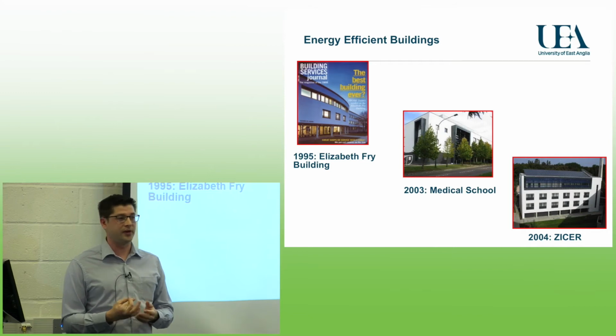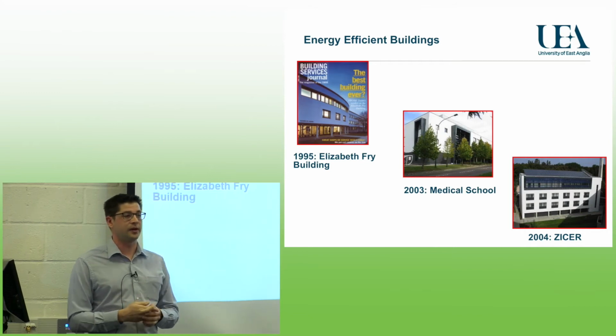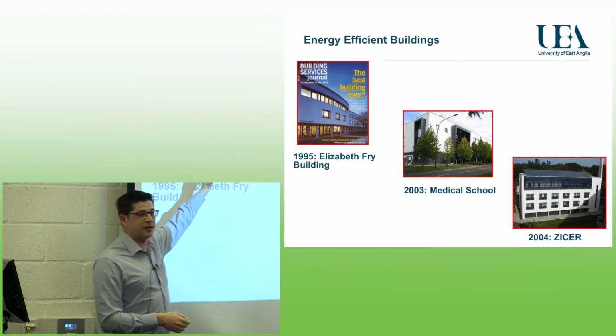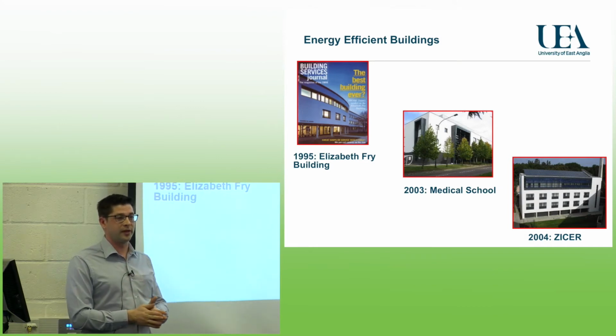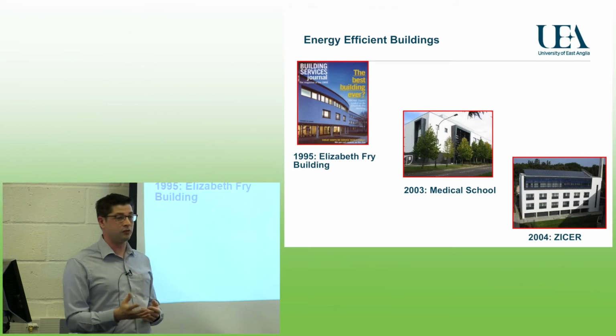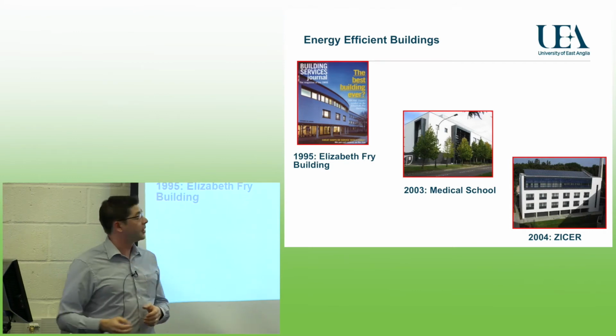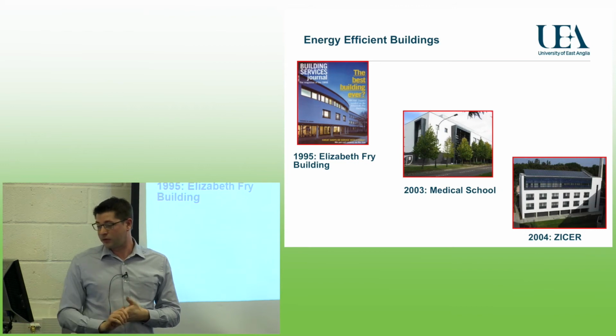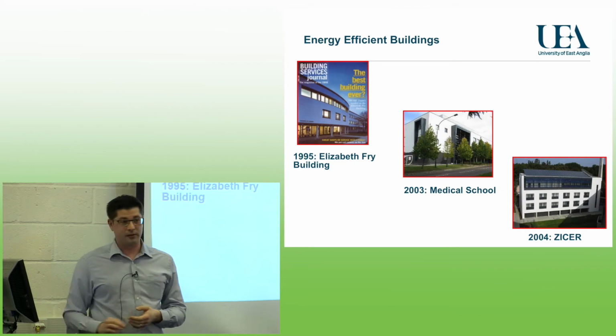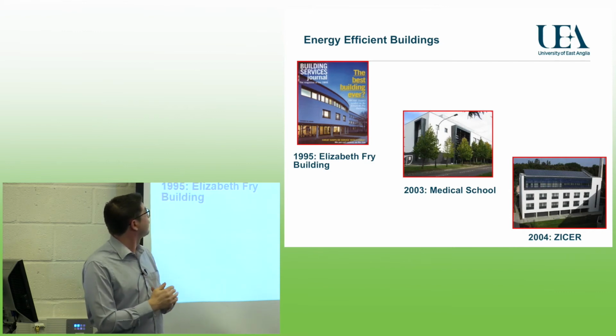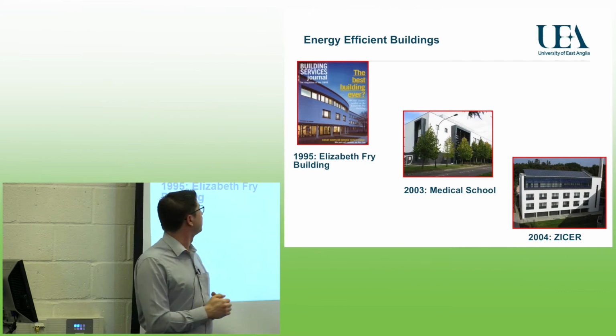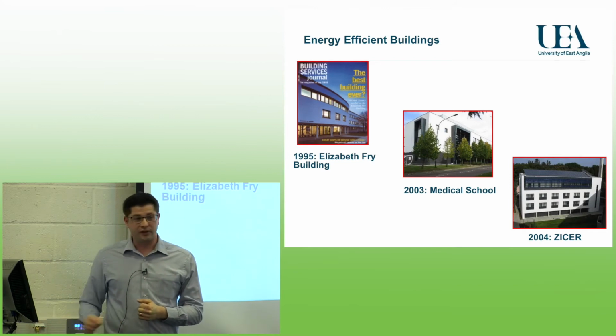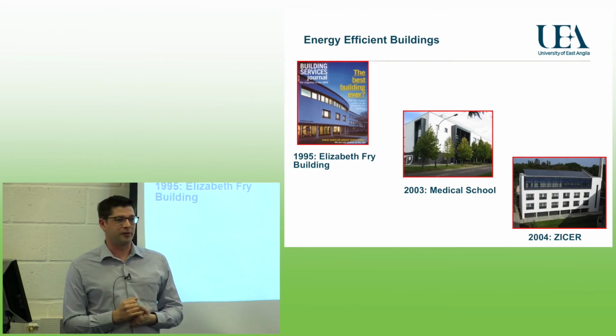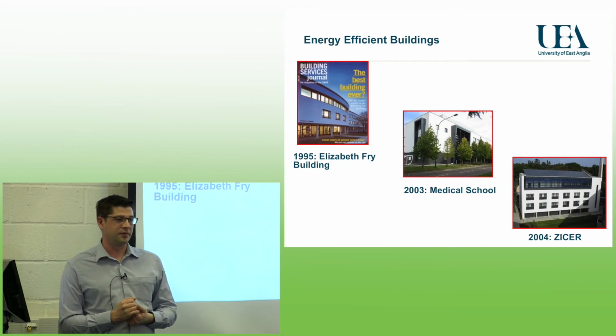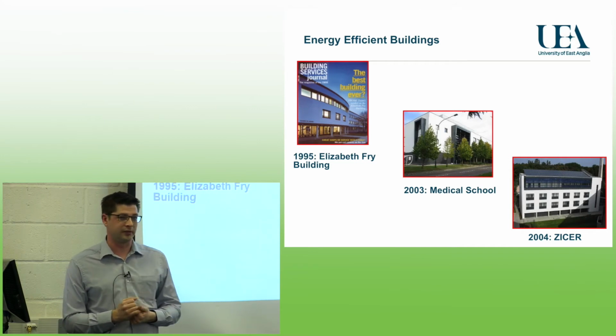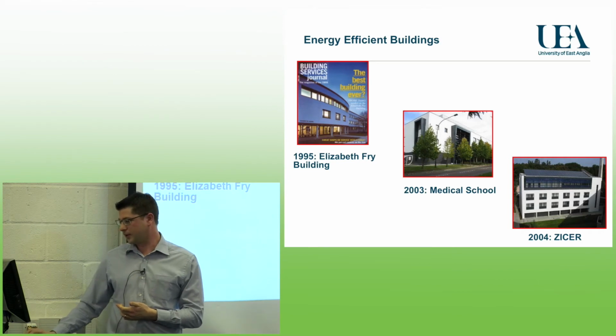Who lives on the village on the campus? Anyone live on the village? Yeah. So this building, 3,500 square metres, had 3 boilers like you've got in your kitchen, and generally only used one of them to keep warm. It's still one of the most efficient buildings on campus. When they did a buildings review of it, it came back as probably the best building ever. For those interested in the numbers, it uses 35 kilowatt hours per metre squared per year to heat, compared to the teaching wall, which uses about 180 kilowatt hours per metre squared to heat.